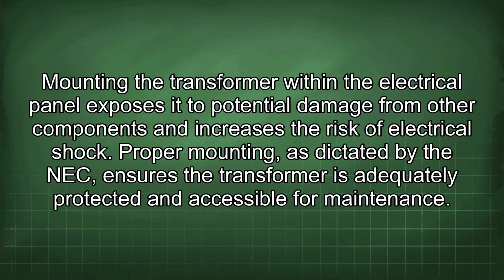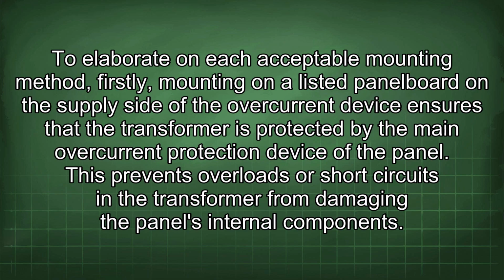Mounting the transformer within the electrical panel exposes it to potential damage from other components and increases the risk of electrical shock. Proper mounting, as dictated by the NEC, ensures the transformer is adequately protected and accessible for maintenance. To elaborate on each acceptable mounting method, firstly, mounting on a listed panel board on the supply side of the overcurrent device ensures that the transformer is protected by the main overcurrent protection device of the panel. This prevents overloads or short circuits in the transformer from damaging the panel's internal components.